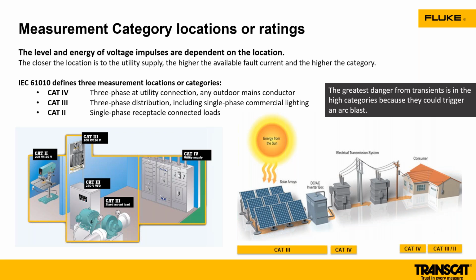If you look at category 4 environments, these are part of the utility. These are basically out on the lines, out into the transformers of the utility. These are typically your 3-phase connections on that side. Once we get into that 3-phase, that Cat 3, it's a three-phase distribution, but it's typically internal to the building. That's where your category 3 environment could be. And as you can see, that voltage can be 480, 208, just depends on what you're working with. And then that category 2 environment is those single phase receptacles that I was talking about, those residential 120 volt, and depending on what you're working on, even sometimes a 240 volt for air conditioners. I've seen plug-in air conditioners have a 240 volt. That's still considered a Cat 2 environment.